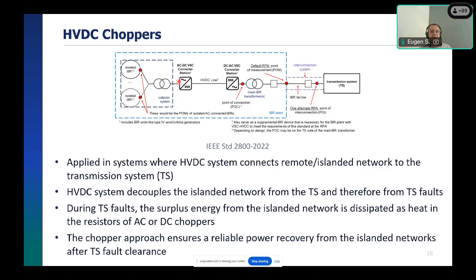Looking at the PRC 029 requirements for fault ride-through, we have definitions in attachments 1.7, 8, and 9, which define the fault ride-through scenarios. It's very similar to IEEE 2800, but the problem is that as written, the criteria limit the number of fault ride-through cases within a 10-second time period, but don't define the number of these 10-second periods, meaning a fault scenario can happen every 10 seconds.